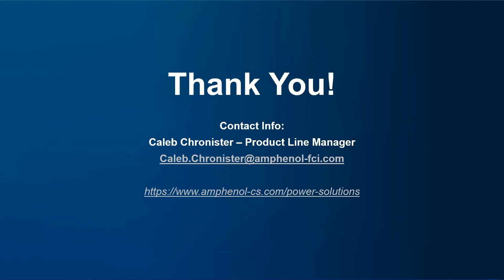That is all I had for my presentation. If anybody has any questions, now would be a great time to ask them. The first question: what are the sense contacts on the BK-150IO used for? The BK-150IO sense pins are used in tandem with the system's intelligence, and will detect if the power connector is being unplugged while power is still flowing. For high-current power connectors, it's pretty important, because when hot plugging occurs it will result in arcing, which can damage the connector. It works with the system's intelligence and cuts the power before it's unmated, preventing any damage that could be caused by arcing from the connector in the bus bar.